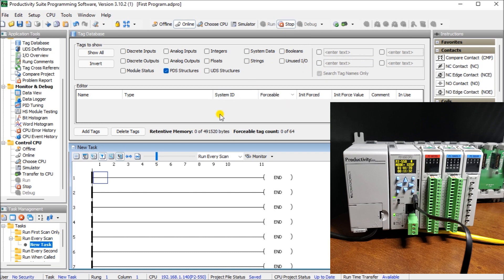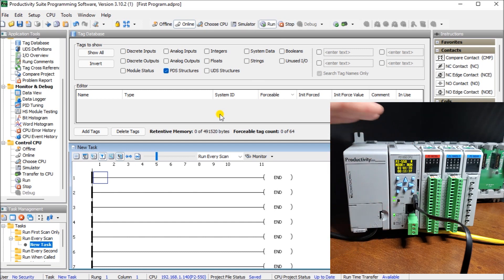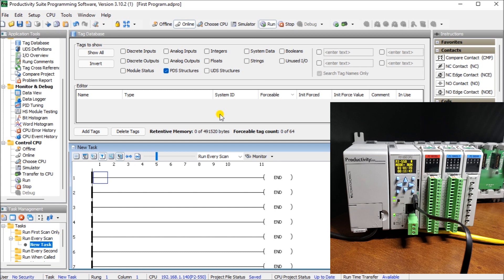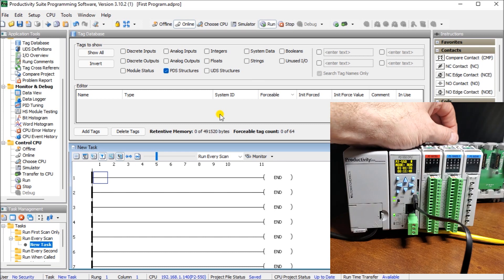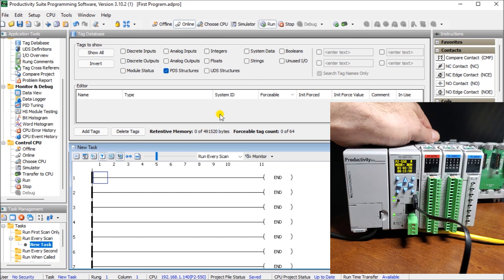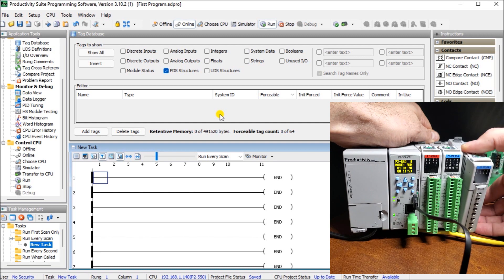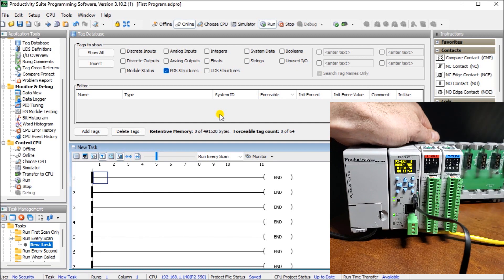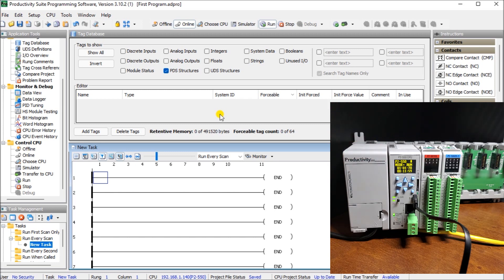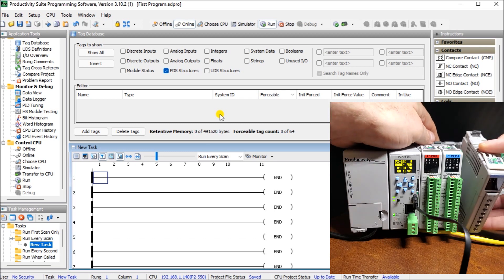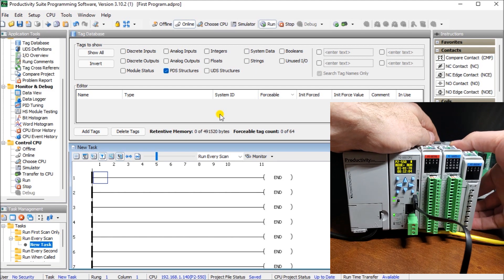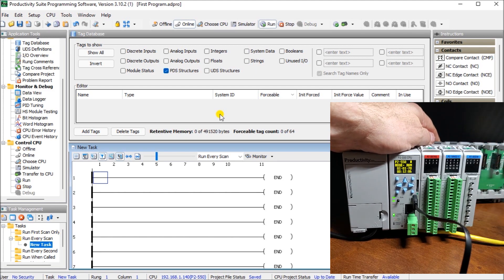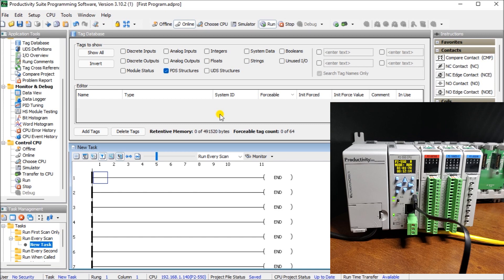We could go over now and flip the switch. And now we are in run mode. And remember in run mode, we said that we can literally unplug this now, this hot swap without that going off a run. So let's just try that out. We can unclip that simulator card and we'll pull that down and off. And you can see that we are still in our run mode. We haven't created any errors at all. And we can replace that card. And then lock that card back in. There we go. And you see our PLC is still up and running and running well.